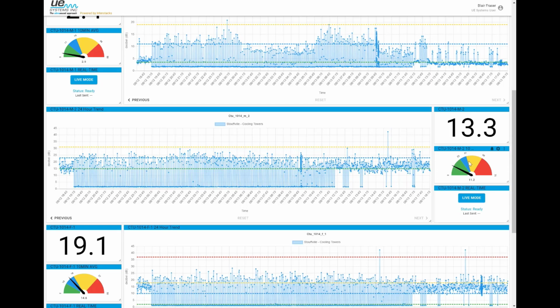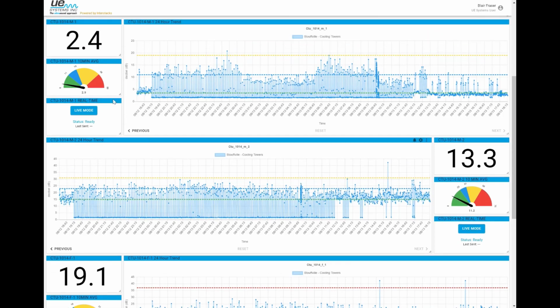If it had been in the blue zone, that indicates it needs lubrication; if it was in the yellow, the early onset of failure; and red is a critical failure. I can do this for the motor inboard bearing as well. As I can see, I am reading 2.9 with a baseline of 3. I am at my baseline, which is great.